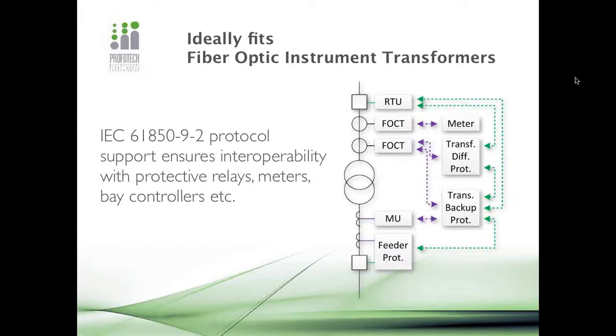You can see the merging unit, which is the analog to digital converter with IEC 61850-9-2 interface. And we can see the feeder protection unit. So all of these devices can communicate with each other using only digital communication protocols.